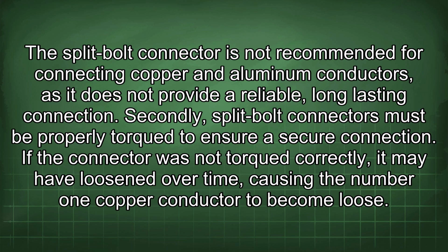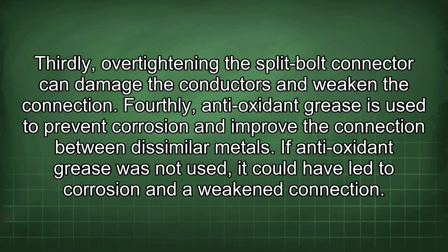long-lasting connection. Secondly, split bolt connectors must be properly torqued to ensure a secure connection. If the connector was not torqued correctly, it may have loosened over time, causing the number 1 copper conductor to become loose. Thirdly, over-tightening the split bolt connector can damage the conductors and weaken the connection. Fourthly, antioxidant grease is used to prevent corrosion and improve the connection between dissimilar metals. If antioxidant grease was not used, it could have led to corrosion and a weakened connection.